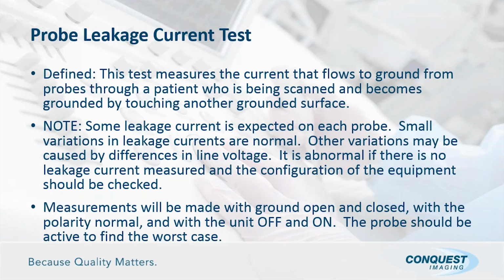It measures the current flow to ground from probes through a patient who's being scanned and becomes grounded, or by touching another grounded surface such as a bed rail that is an electrical bed that is grounded. So at that point, if there is leakage, it'll flow through the patient. Some leakage current is expected on each probe. Small variations in leakage currents are normal. Other variations may be caused by differences in line voltage. It is abnormal if there is no leakage current measured, and the configuration of the equipment should be checked.